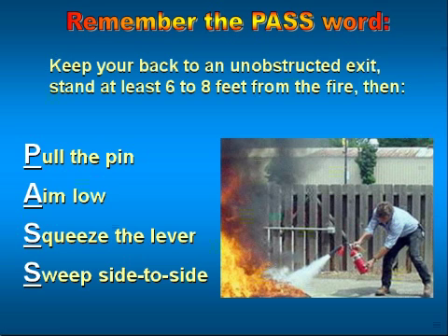Keep your back to an unobstructed exit. What we're saying here is that as you go to try to deploy a fire extinguisher, or to egress out of a building using a fire extinguisher to help you get out, you never want to turn your back on something that's burning. If you put the fire out, you continue to face it and back out the doorway. That way, if it reignites or if you have a flashover, you're facing it. You're not getting burnt from the backside.